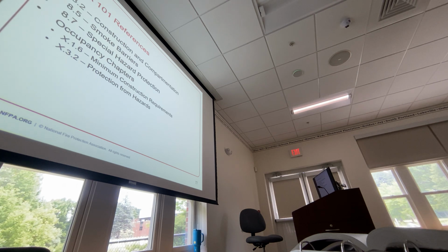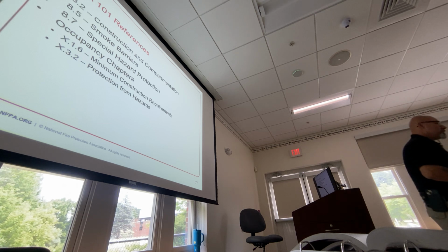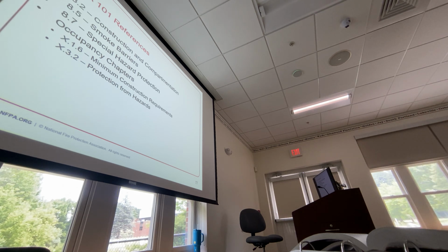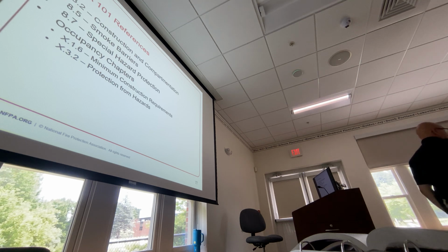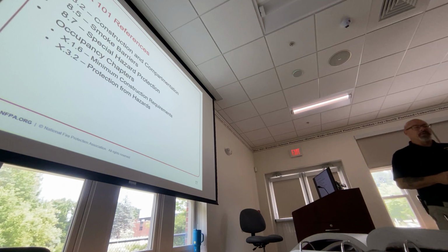Table 18.1.6.1, to be exact. This is new, so 18, new healthcare occupancy. I have a type 5, so you're looking at your construction type. Type 5, you can do 111, 3 stories. What does 3 stories tell us for a type 5 111, or type 5 even, for that matter? Not permitted. NP, not permitted.